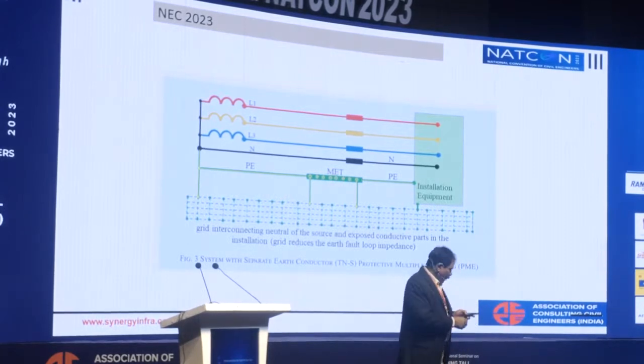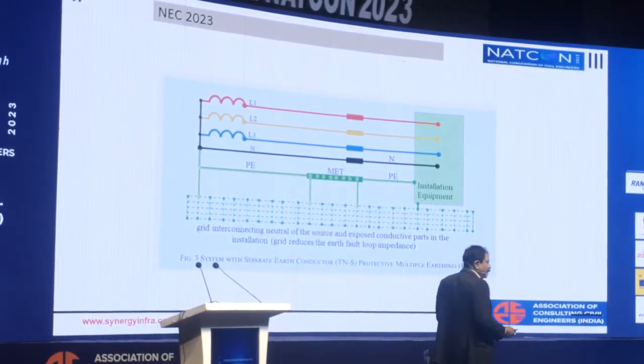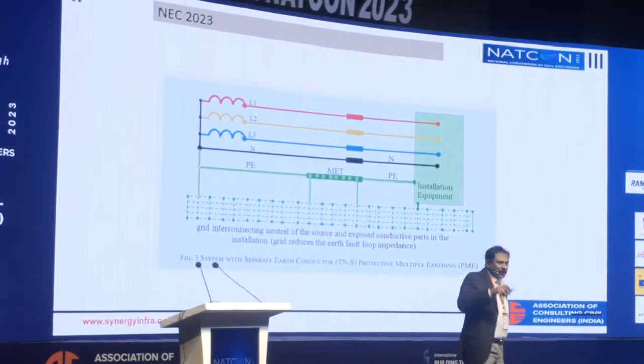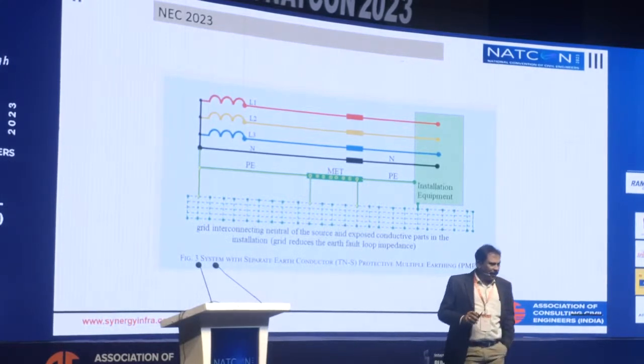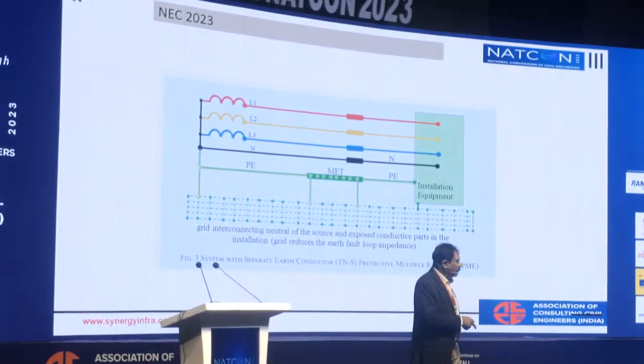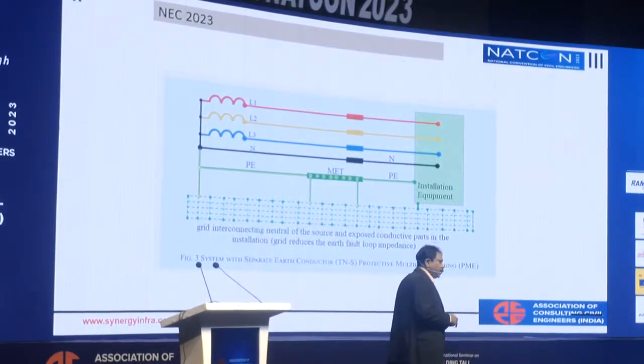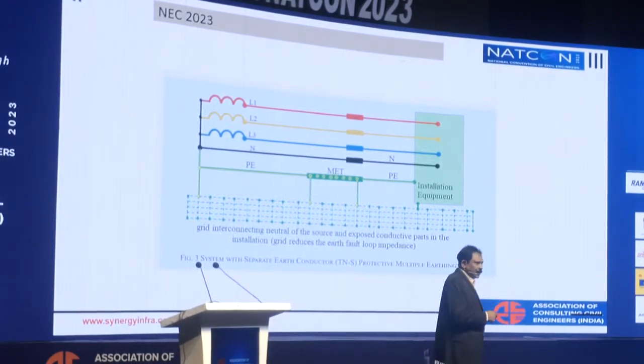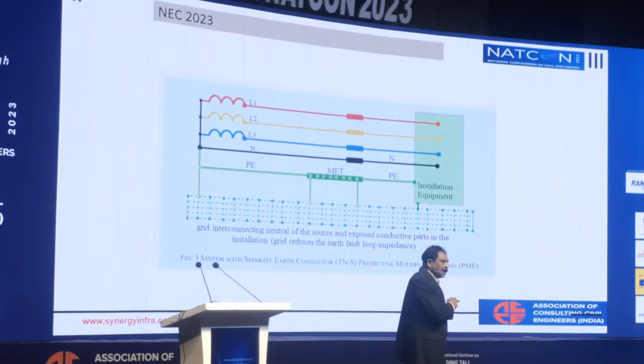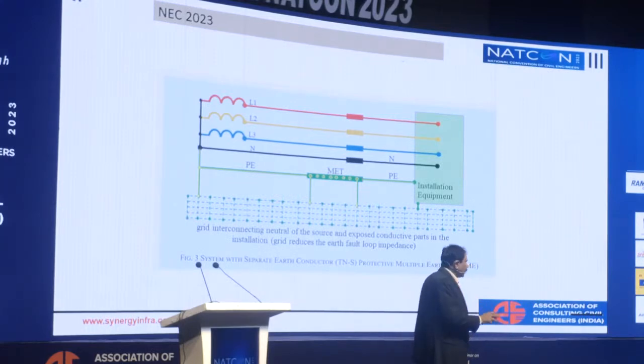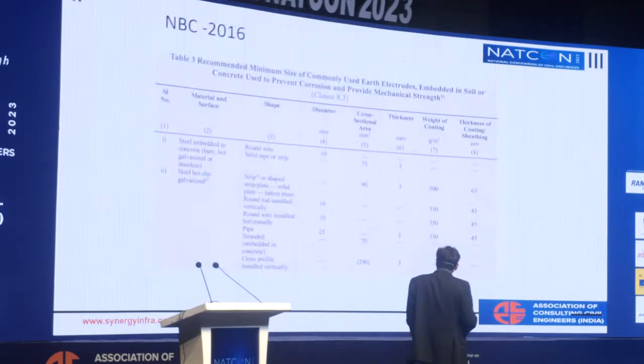Even now we face problems with elevator manufacturers: "My lift should have two separate earthings, otherwise I will not give any guarantee." But even that has been addressed in the National Building Code of 2016 under elevators and escalators, vertical transportation systems, which says the entire elevator should be connected to the building earth. So we are not supposed to maintain anything separately.